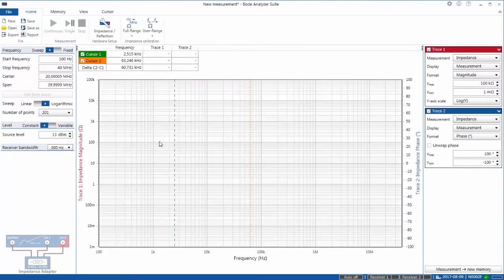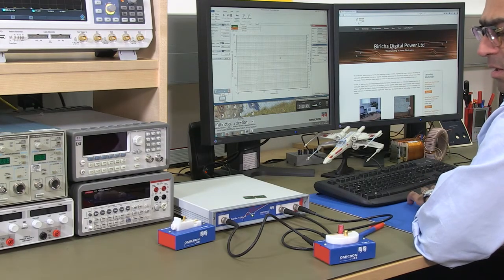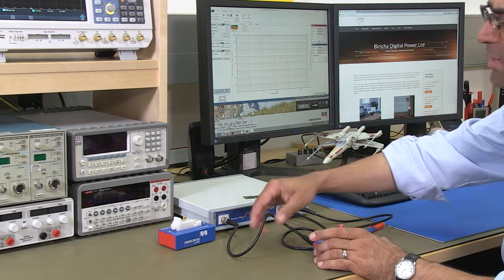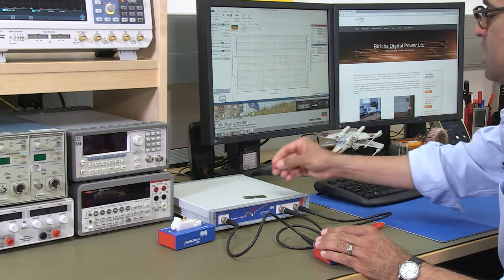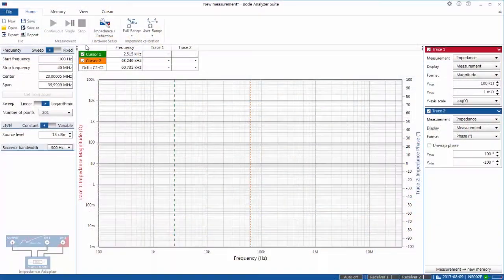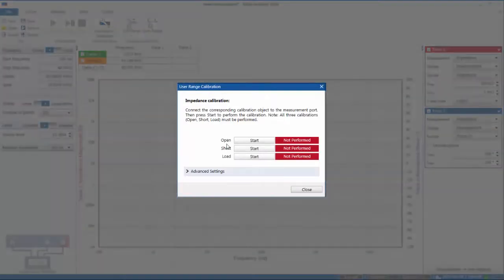After you've clicked that, this is the screen that will open. Now it is at this point that I must stress it's very important to calibrate the instrument so that it will negate the impact of all these cables and the actual box. Here we're going to do a user calibration. So you get three options: open, short, and load. Open is when the impedance adapter is open-circuited, so there's nothing in it, and you just press that.